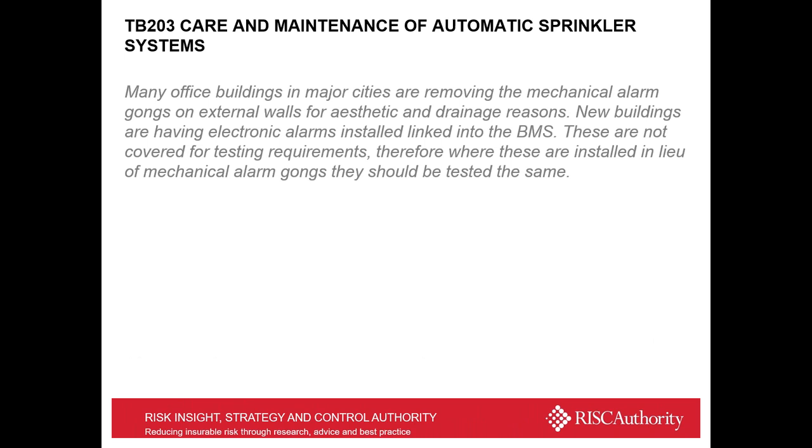So moving back onto TB203. As mentioned, there are many office buildings in major cities moving away from mechanical alarm gongs. Architects don't want to see them. They're in positions where they can't be seen. Valve sets are being located down below basements, and there's a limitation on the pipe run to the mechanical alarm gongs. There's drainage of water issues below ground.